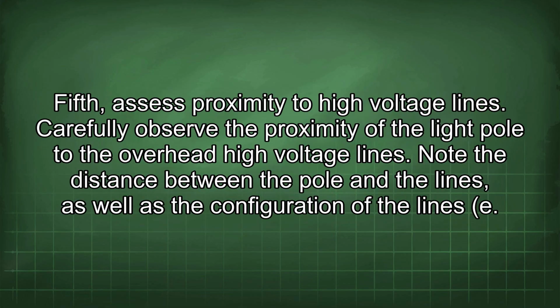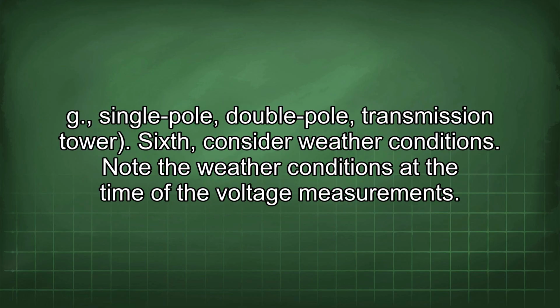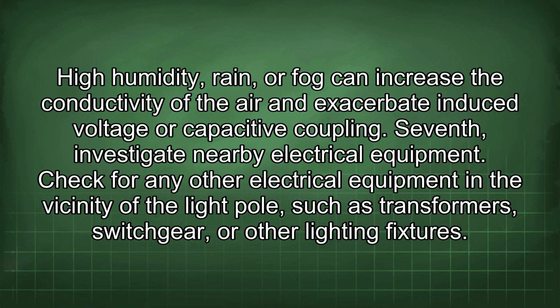Fifth, assess proximity to high voltage lines. Carefully observe the proximity of the light pole to the overhead high voltage lines. Note the distance between the pole and the lines, as well as the configuration of the lines, e.g. single pole, double pole transmission tower. Sixth, consider weather conditions. Note the weather conditions at the time of the voltage measurements. High humidity, rain, or fog can increase the conductivity of the air and exacerbate induced voltage or capacitive coupling.